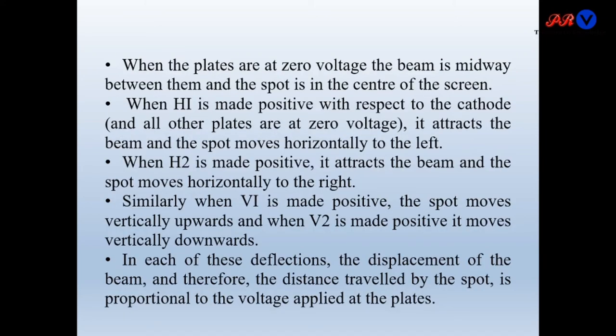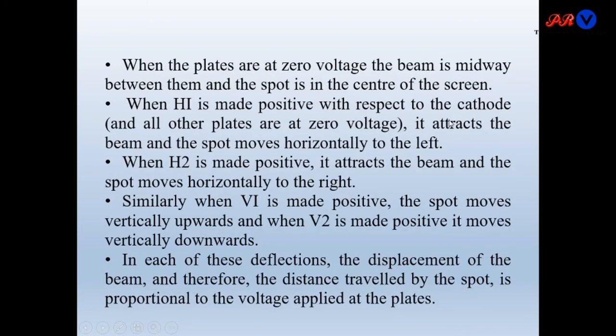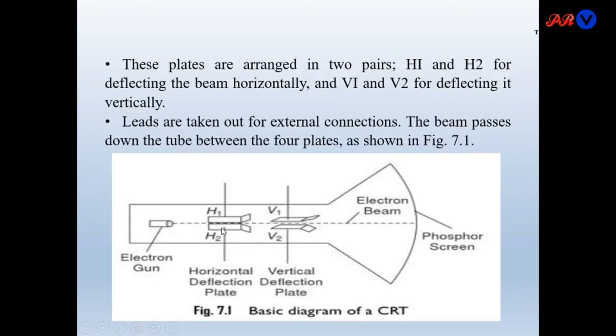Now we will discuss how these plates affect the spot position. When the plates are at zero voltage, the beam is midway between them and the spot is at the center of the screen. When H1 is made positive with respect to the cathode and all other plates are at zero voltage — H1 being on the left side of the tube — it attracts the beam and the spot moves horizontally to the left. When H2 is positive, then the beam will move to the right.